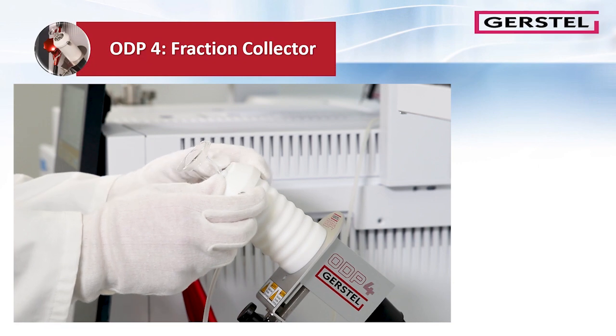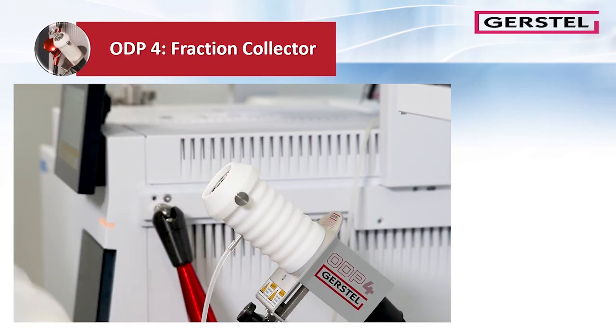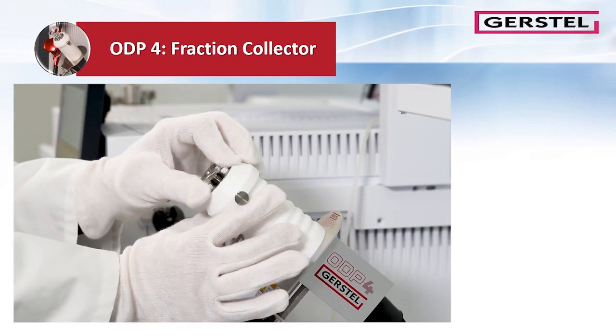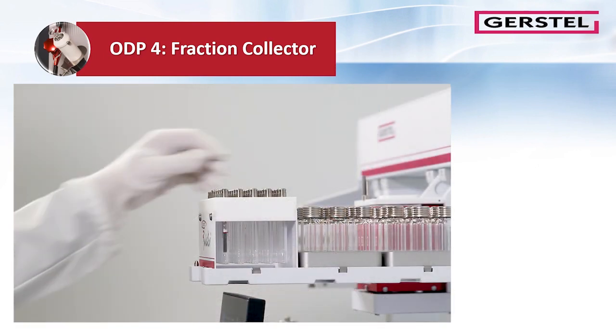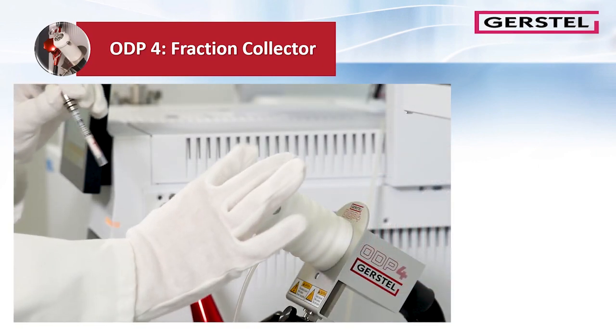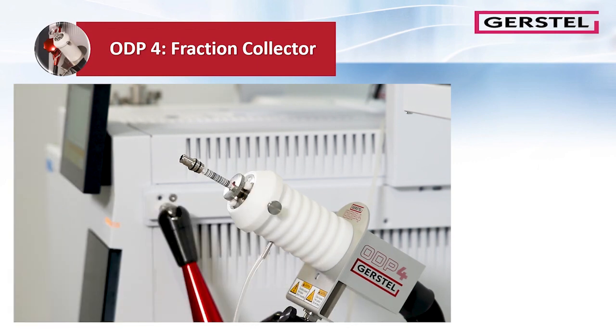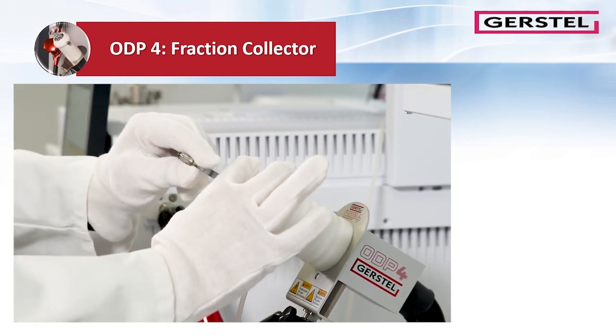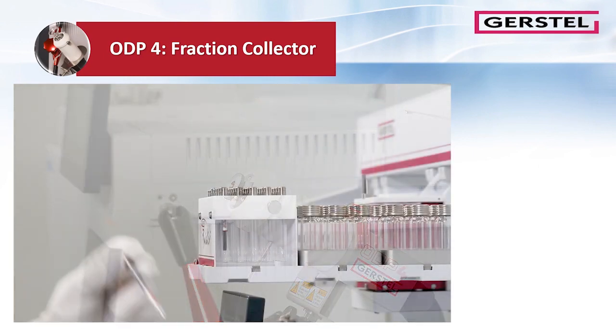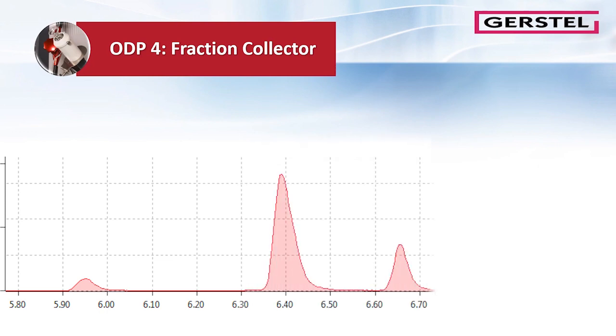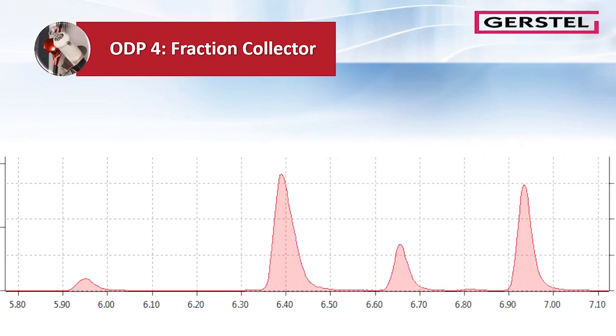The conversion is very simple. The glass cone and the Teflon disc are removed and the adapter is used for the trap. The trap tube is now inserted at the time of the coeluting peaks. After collecting the peaks of interest, the tube will be stored on the tray. Then we run the coeluted analytes from the first example on a different column and got baseline-separated peaks.